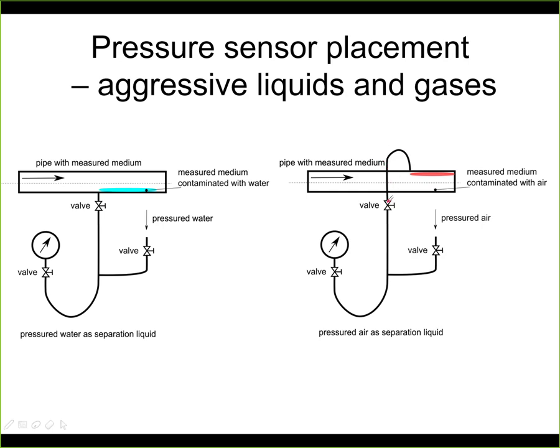The exception is that here, in the case of a gas, it's actually going from the top of the pipe, so that if there are some sediments and impurities here, they will not enter into this system. So again, this system is filled with pressurized air. The air is blowing constantly with some given flow. It's going into the pipe, and this whole system is filled with air. And again, if this pressure is changing, it gets transferred through this system into the gauge, and we can measure this actually.